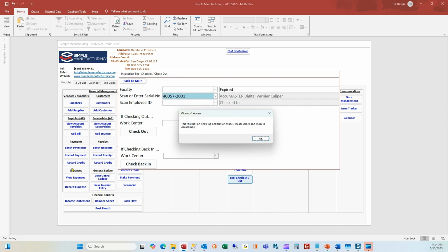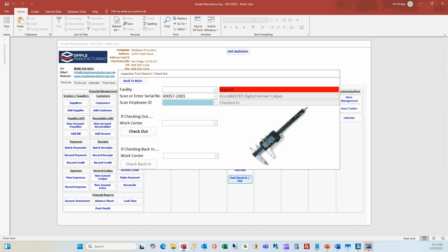Red flags occur when a device's calibration is past due, or the device has been flagged as inactive, lost, or taken out of service. Once alerted, users decide on the action to take, whether updating the device's status, returning it, or continuing with checkout. If a picture has been added to the device record, it will display.